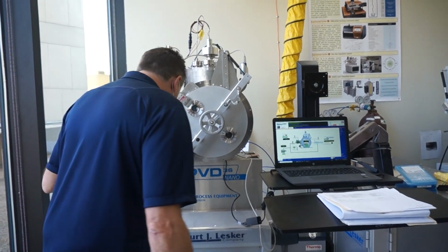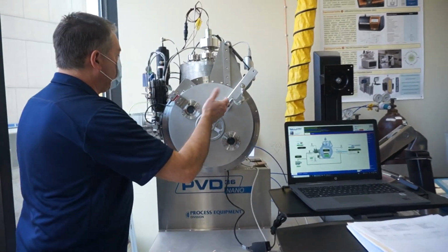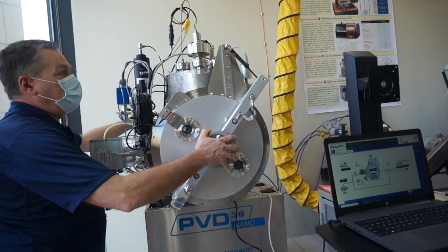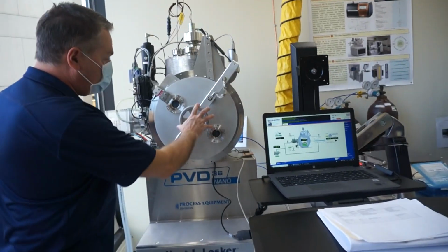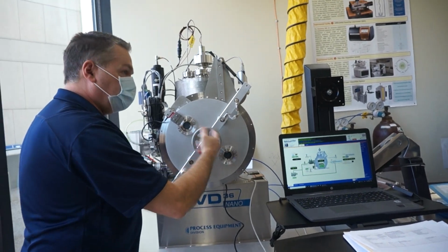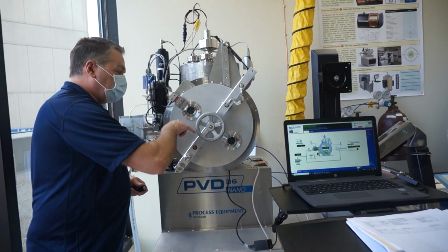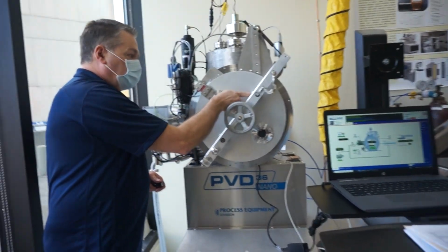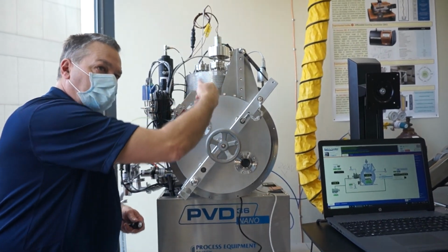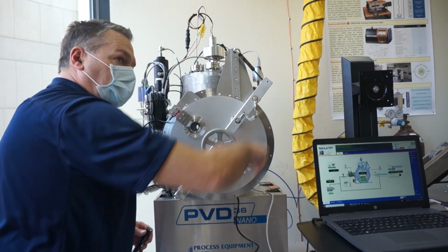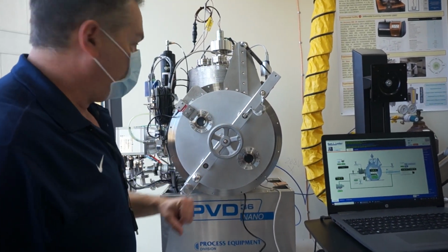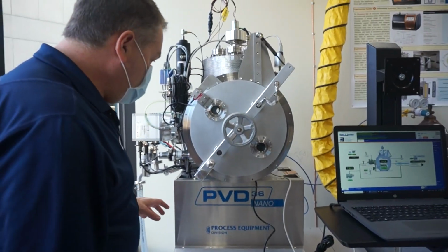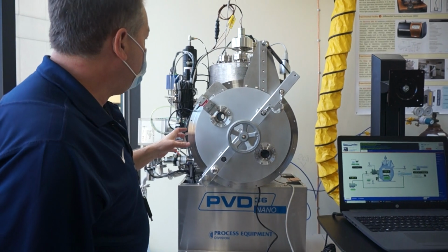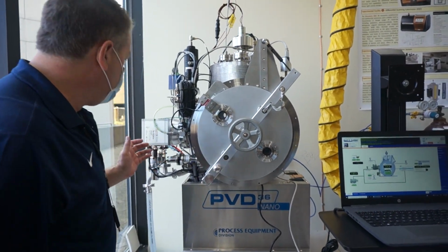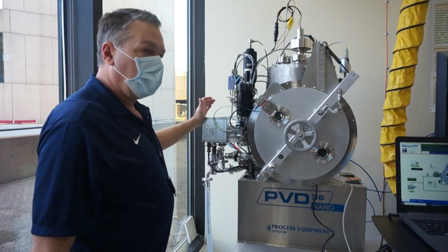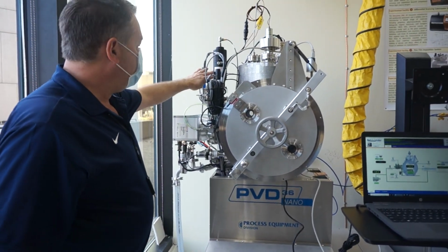So we have two doors on this tool. This door, sometimes in the back we have a blank, but that also has door access, kind of like a submarine hatch. So once you vent the tool, you loosen this, there's a ball screw, the door will slide out. You don't have to crank it the whole way, you just have to get a gap of separation, and then you grab this ball and you kind of open it and it gives access to the tool. We'll go through and I'll show you how to do that. But this chamber, it's a smaller chamber. It has a couple different features I wanted to go over. So you have a 300 liter per second turbo pump, 3-position high vac valve.